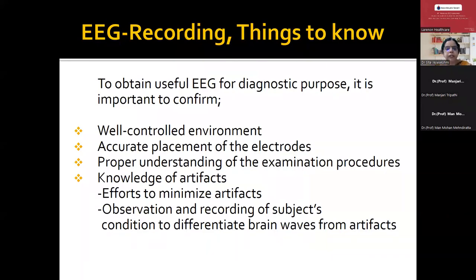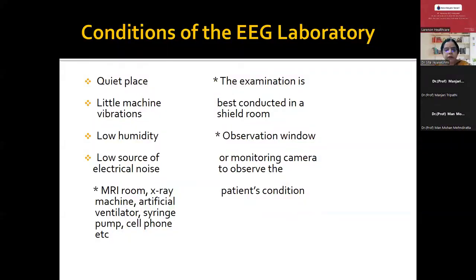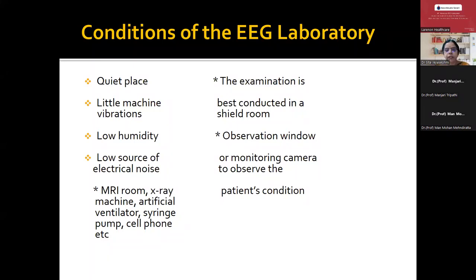Whenever recording the EEG, it should be conducted in a well-controlled environment. Avoid too much traffic in the EEG labs. There should be accurate placement of electrodes, proper understanding of the examination procedure by the patient as well as the technologist, and establishing good rapport is important. The technologist should have good knowledge of artifacts and make every effort to minimize them, with observation and recording of the subject's condition to differentiate brain waves from artifacts. The EEG recording should be done in a quiet place with little machine vibration. Humidity should be low — AC should be on — and low source of electrical noise.